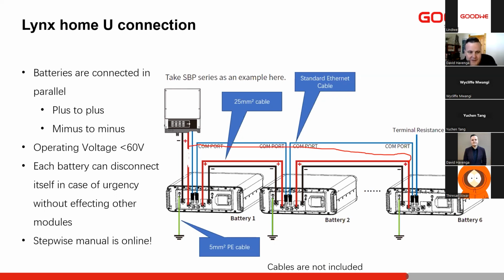I always recommend to install neutral from the one side and live to the other side at the end of the bank. That way you will have equal potential amongst all of your batteries and they can evenly charge without any imbalance. For your communications, you'll go to your first battery like that, and then the rest of the batteries are daisy chained. At the end of the line, we install a termination resistor.